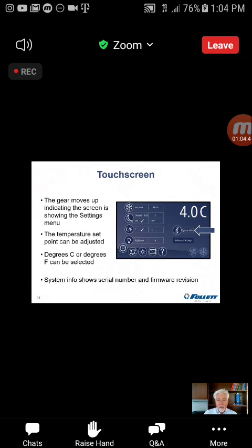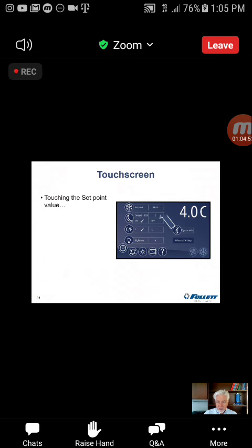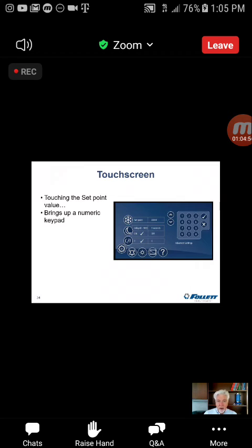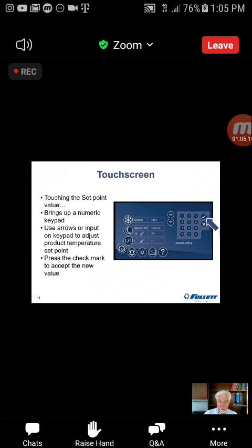Because we won't know what that replacement board is going into. So if we want to adjust the set point, when we touch this, a numeric keypad will show up with some arrows, so we can scroll and adjust that temperature up and down using the arrows, or just enter the number directly into the keypad. The key thing is, when you're done, be sure to hit the check mark to accept the new value. If you don't do that, it's going to stay at the previous setting. It's not going to adjust, even though you changed the number that was in the display.